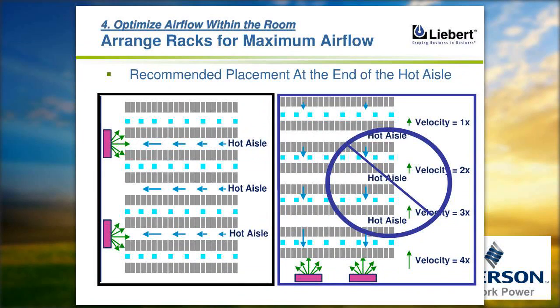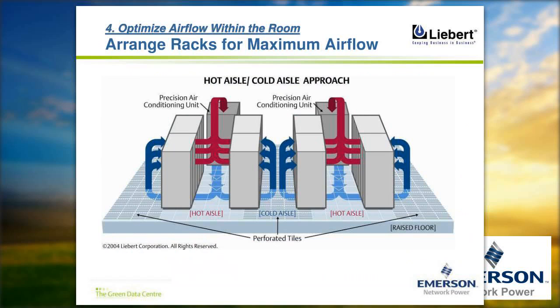Now, if you look at layout, it is expected that high density racks should be kept in the center of the system. Even the placement of the precision cooling unit should be perpendicular to the aisles. They should not be parallel, because that might affect the overall airflow below the false flooring. We recommend a 7-pitch layout. 7-pitch layout means the center of one cold aisle to the center of the second cold aisle will have 7 tiles. And that's how the overall placement, from a perspective of airflow, from the convenience of maintenance, placement of all devices will work quite well. So anytime when you are designing a new data center or upgrading a data center, see to it that you maintain that 7-pitch. Center to center cold aisle should have 7 tiles.